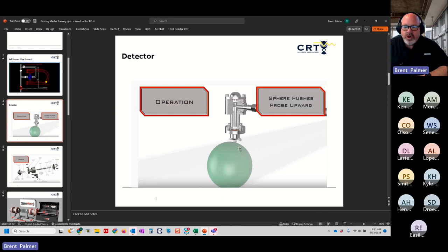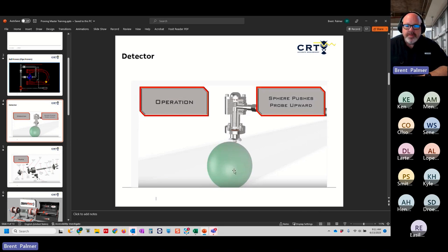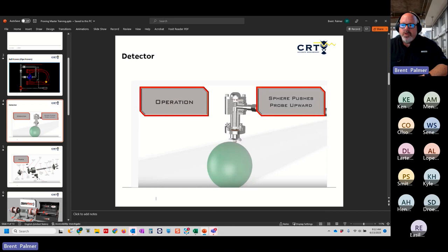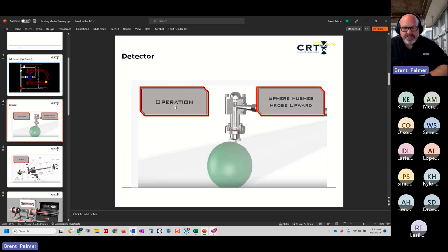Changing the probe extension changes the volume of the prover, so we need to be aware that changing detector switches on ball provers can drastically affect the volume depending on how they're reinserted — you may have to re-water-draw the prover. Also, the ball can travel at such high velocity that the switch will vibrate and bounce — hitting and bouncing up again — causing a false detection. We have settings that allow us to ignore what we call 'detector slap,' adding a delay so that if we see the detector switch we ignore the next input for a set number of seconds.